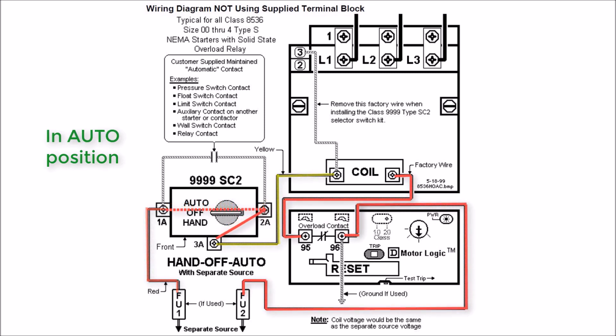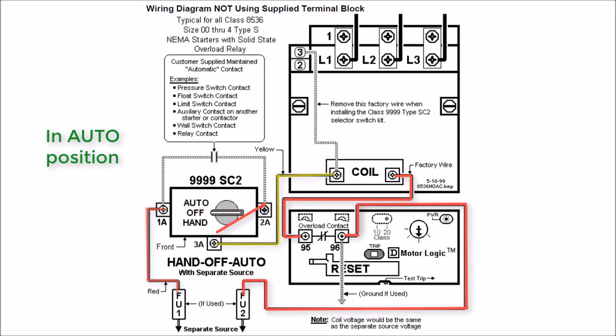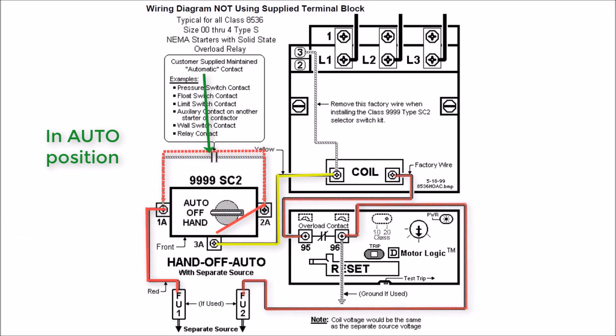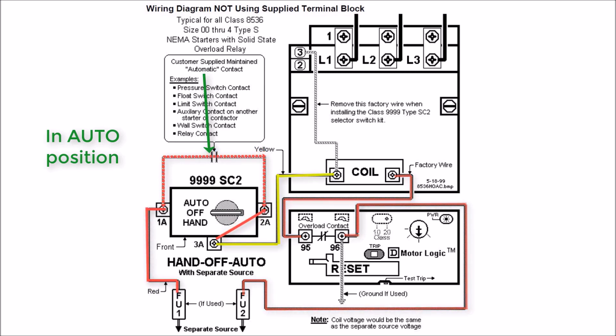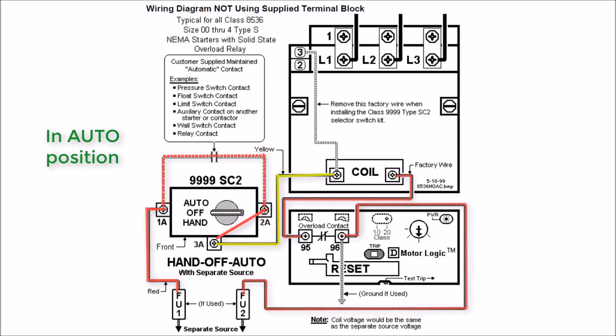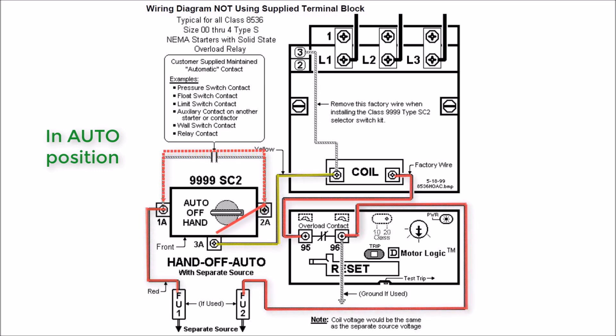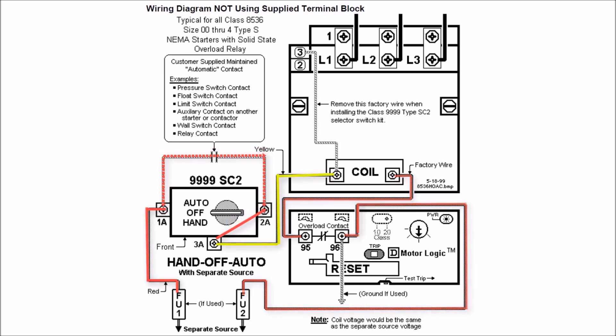In auto, you'll actually have 1A and 2A open with 2A to 3A closed. Your connection point is going to be your automatic source, so a float switch, a limit switch, or pressure switch. You're going to wire out from 1A, which is carrying your hot leg in this instance, to your switch, your normally open switch, then back to 2A, which is going to be your control source.